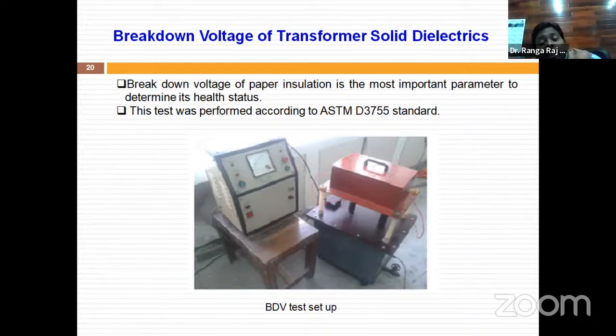So we should test the dielectric strength of the paper insulation before manufacturing the transformer, before wrapping it on the winding. For this solid dielectric test, we generally use this test setup to determine the dielectric strength of the paper. The test is performed according to ASTM D3755. It is a very simple test setup.